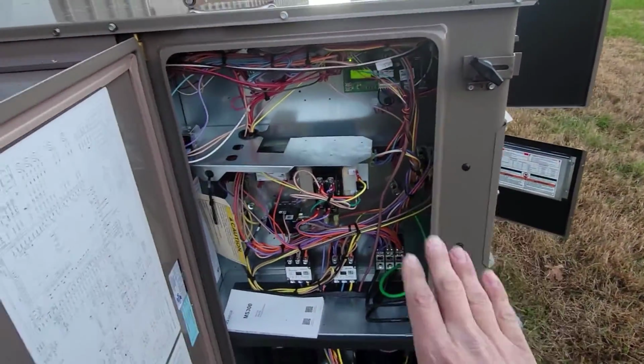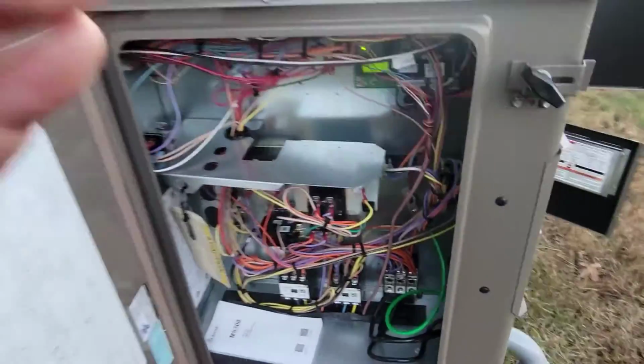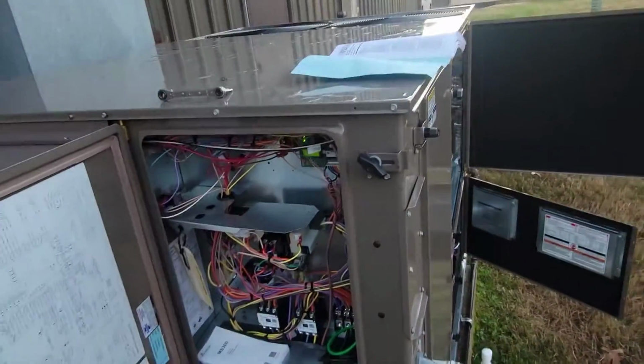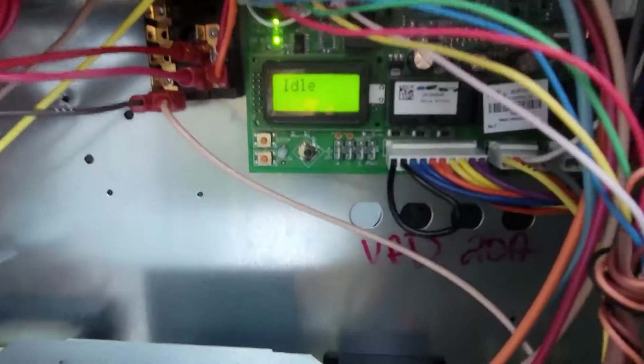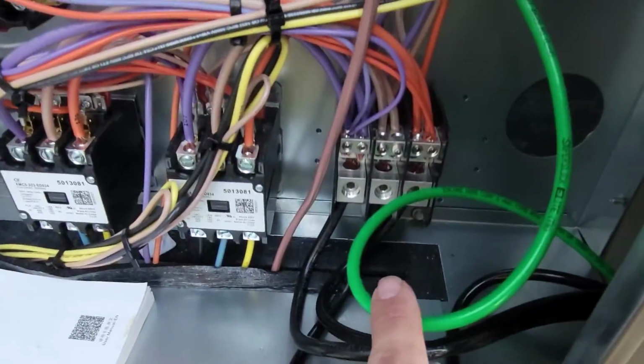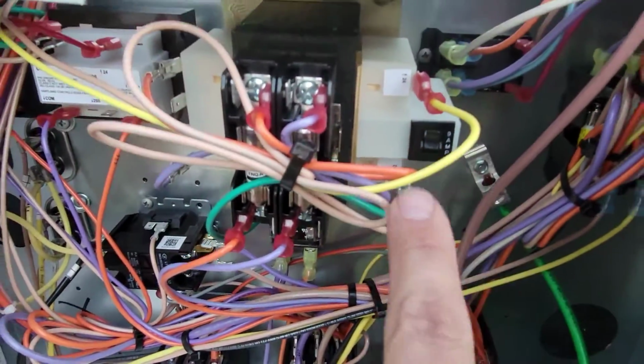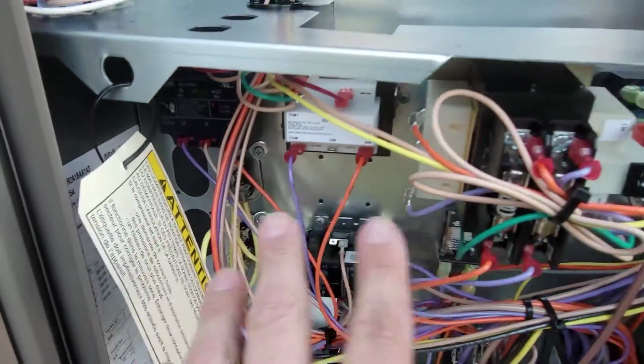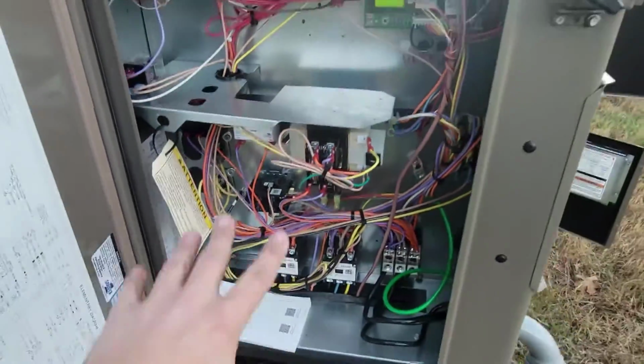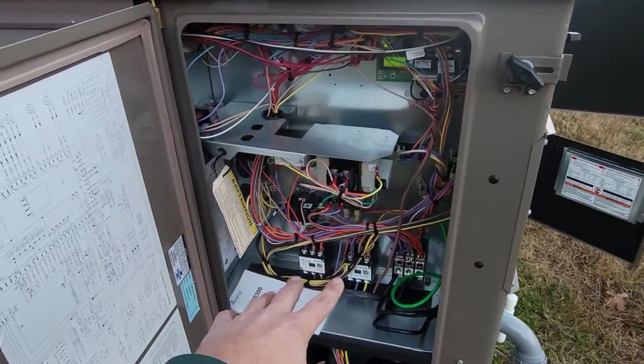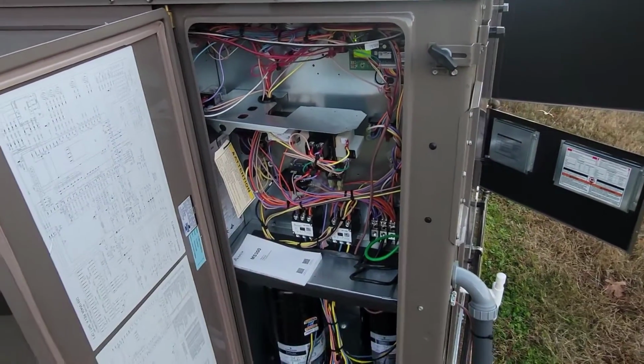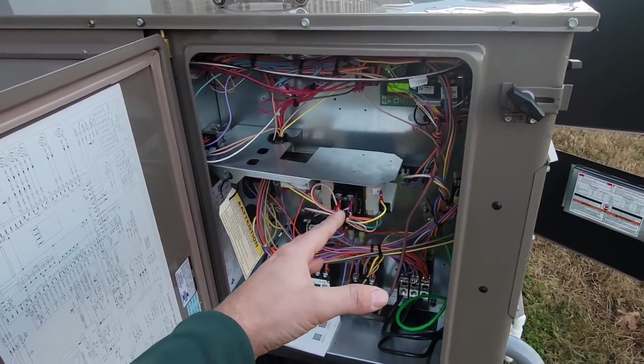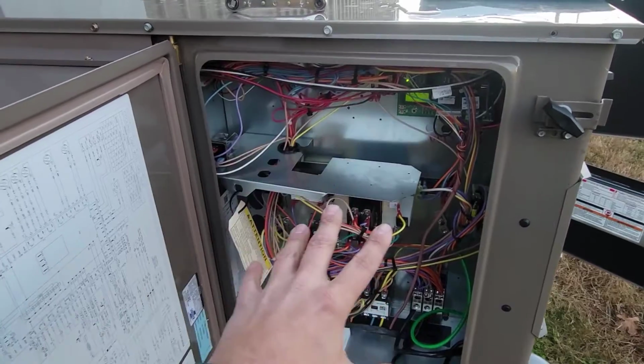So that is the first tip I'm gonna give you. If you ever start up a new commercial package unit made by York and you don't have any display, check and make sure you have your voltage coming in, and then your 24 volts off your transformer. If you don't know how to check that, check out my playlist, I've got a video on relays, checking power, and how to wire thermostats. You need to check that out. So that's the first tip that I want to give you.